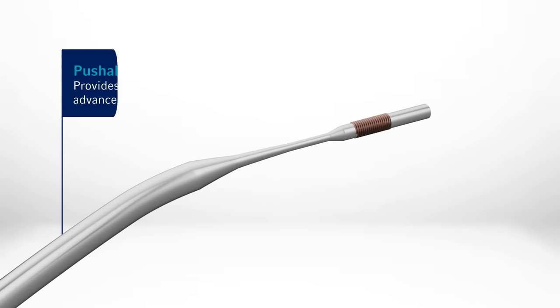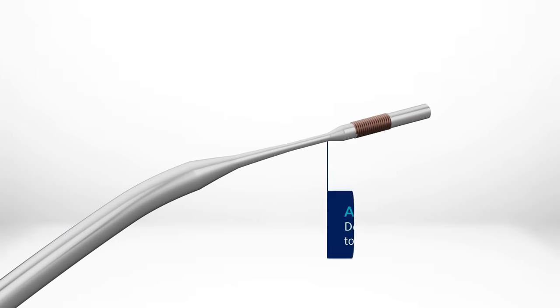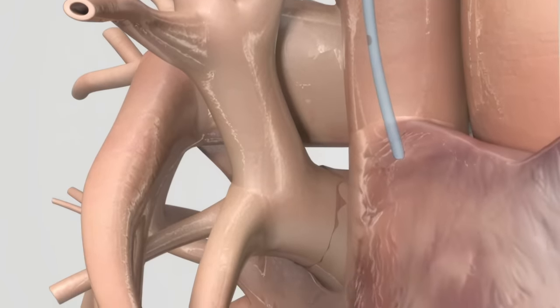The stylet features a pushable body with a short flexible section, plus an angled tip and an anatomical curve that allows the stylet to self-orient to the human anatomy, directing the PICC toward the SVC for optimal deliverability.